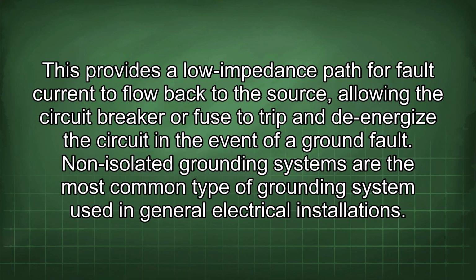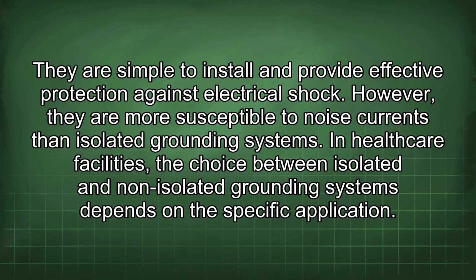This provides a low impedance path for fault current to flow back to the source, allowing the circuit breaker or fuse to trip and de-energize the circuit in the event of a ground fault. Non-isolated grounding systems are the most common type of grounding system used in general electrical installations. They are simple to install and provide effective protection against electrical shock. However, they are more susceptible to noise currents than isolated grounding systems.